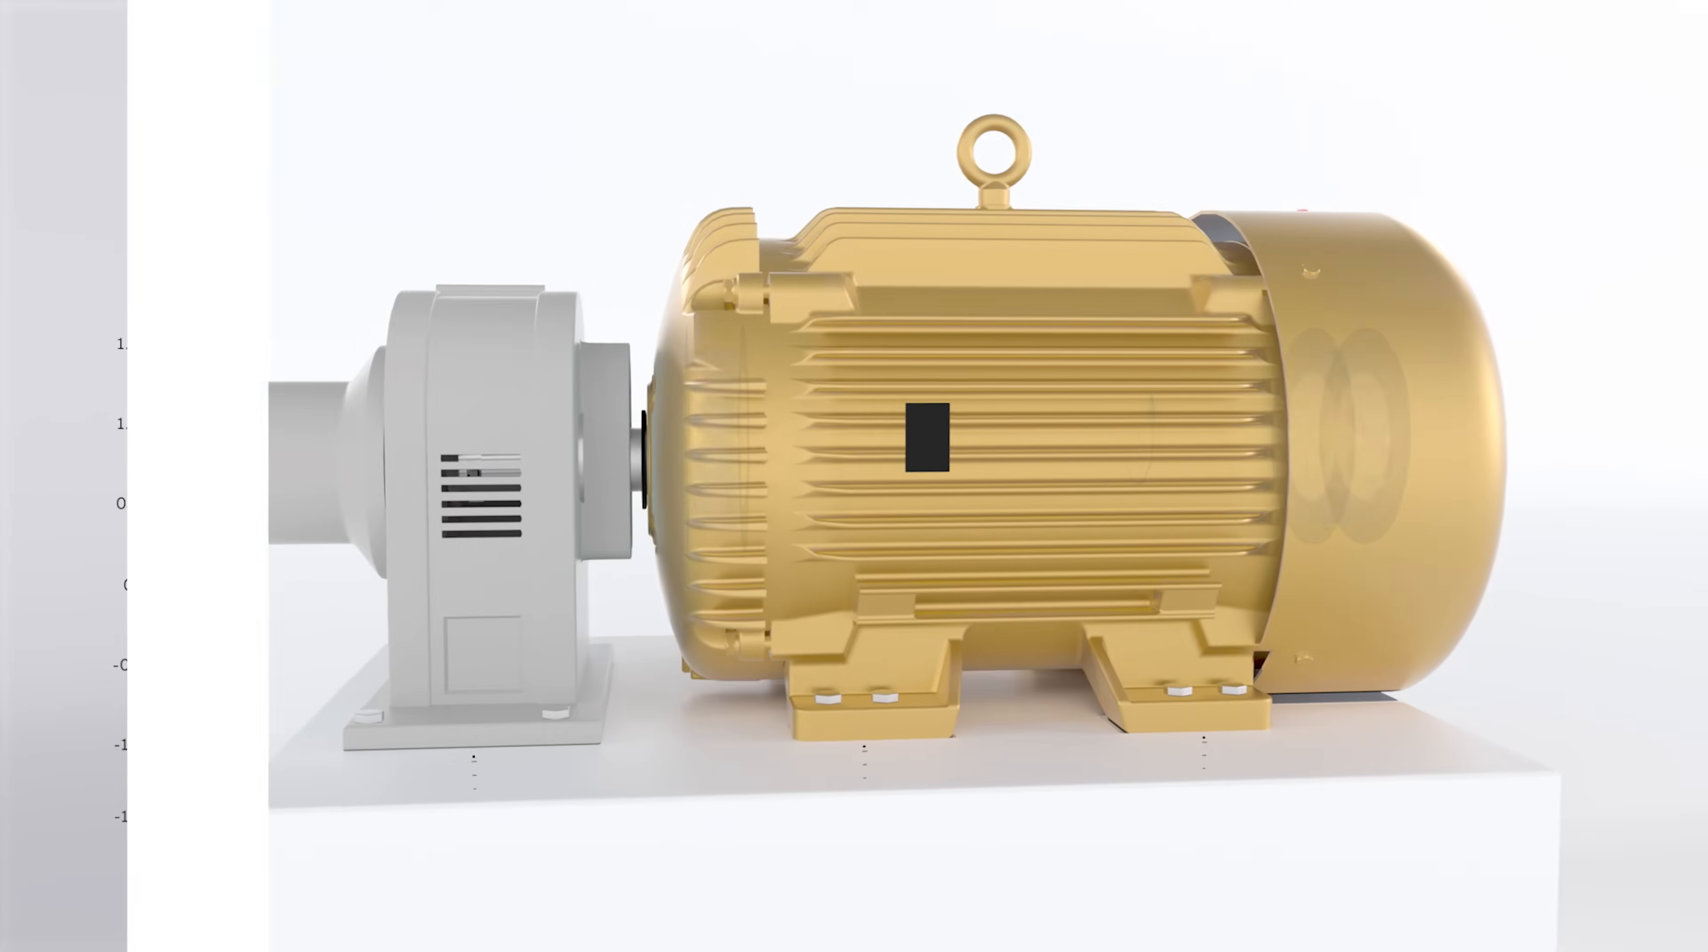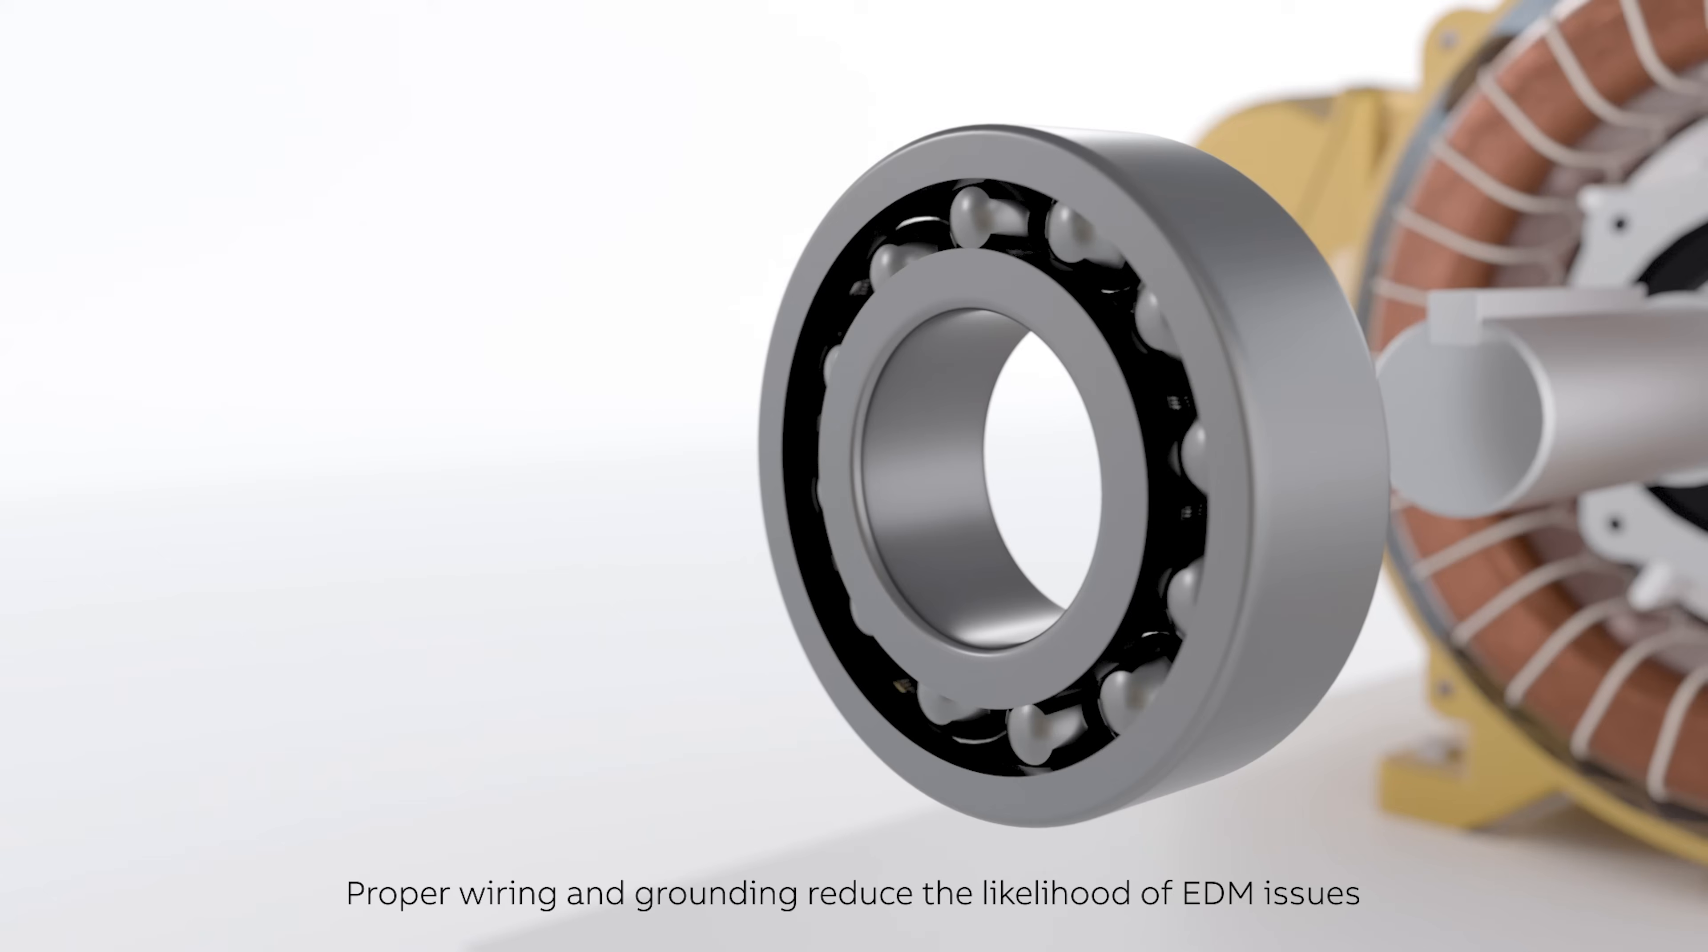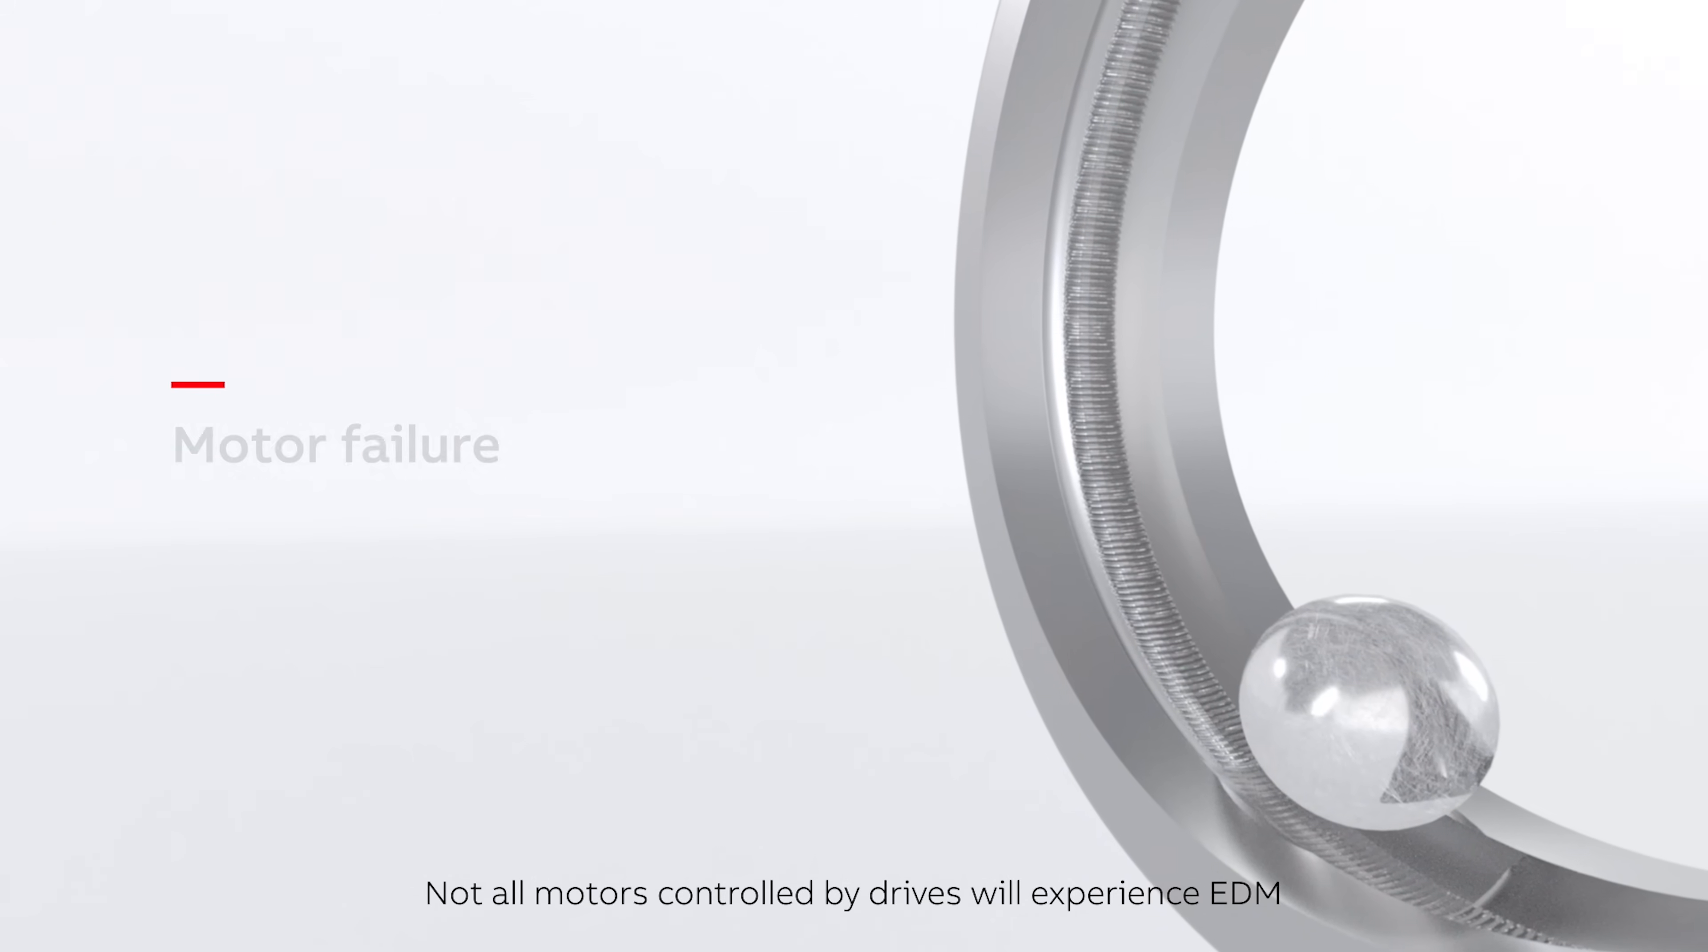Common mode voltage builds up across the bearings due to the dielectric effect on the bearing grease, and will eventually discharge through the bearings in what is referred to as EDM, or electrical discharge machining. Over time, this continual arcing will cause damage to the surface of the bearing race, resulting in vibration and heat, loud operating noises, and eventually motor failure.